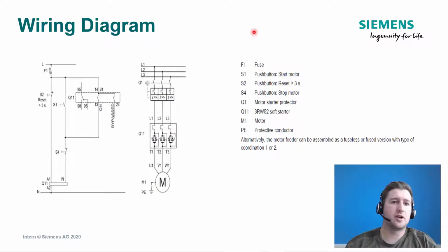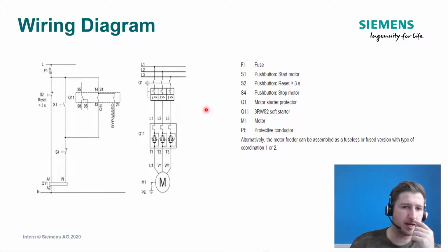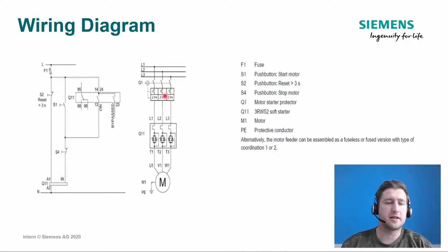This next diagram shows the characteristics of the main circuit and also the control circuit. So in the main circuit, you always have a form of short circuit protection, which is shown here. That could either be a molded case circuit breaker, an air circuit breaker, a motor starter protector, or even fusing. So the standard protocol for a soft starter protection would be dependent on what type of short circuit protection you want to achieve, whether you want type 1 or type 2 coordination. This demonstrates type 1 coordination with a motor starter protector. If you wanted type 2, that's typically done with fusing.